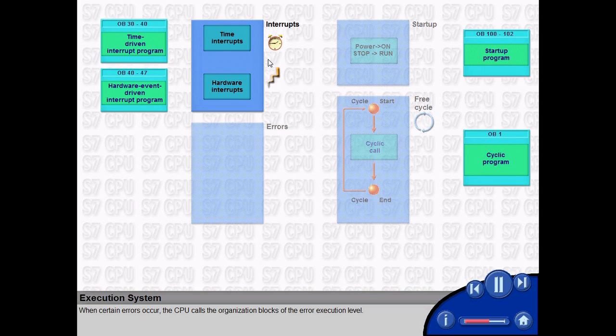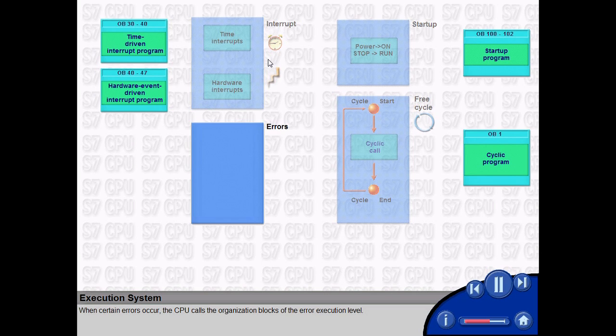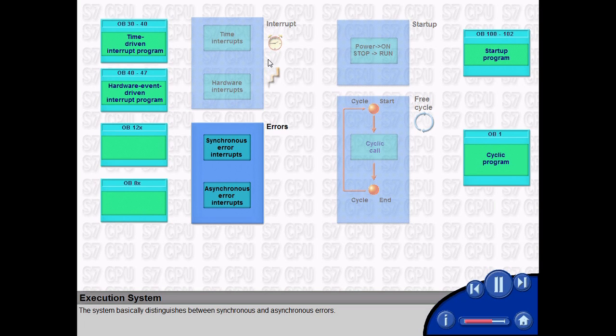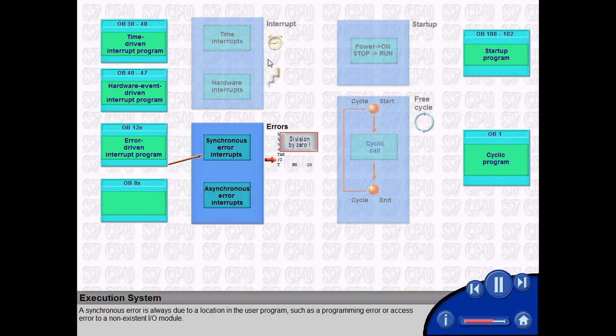When certain errors occur, the CPU calls the organization blocks of the error execution level. The error program you called from the organization block now determines the reaction to this event. The system basically distinguishes between synchronous and asynchronous errors. A synchronous error is always due to a location in the user program, such as a programming error or access error to a non-existent IO module.